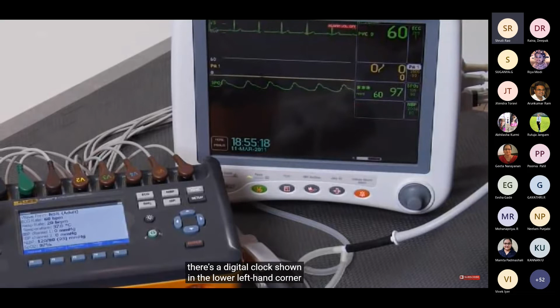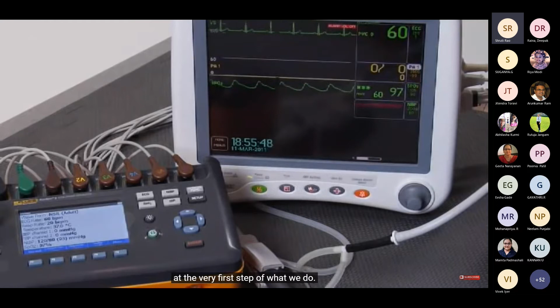As you can see, there's a digital clock shown in the lower left-hand corner of the patient monitor display, so you can be your own judge as to whether we can get through this test within 5 minutes or not. As I begin the test, we are already connected to the device under test. All of the connections have been made ahead of time, including the NIBP cuff. We are going to zero our invasive blood pressure transducers on the patient monitor as the very first step, followed by a selection of a simulation of all coordinated patient parameters.